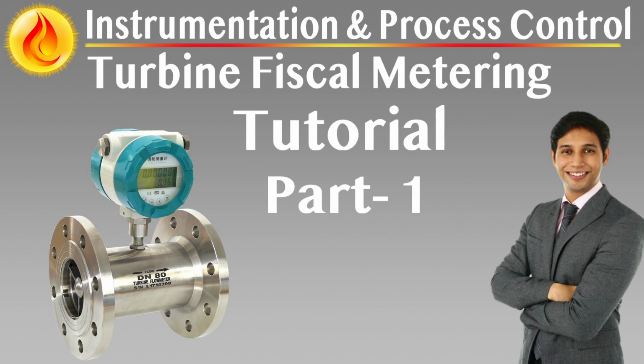At its core, turbine fiscal metering is designed to monitor liquid hydrocarbon flows with rigorous traceability and uncertainty bounds. The system is divided into two subsystems: the field-mounted skid with sampling and proving equipment, and the control and calculation infrastructure located in the CCR, LCR, or local room. This structure ensures operational transparency, enabling cross-verification of quantity, mass, volume, and quality (density, temperature, water cut) prior to final delivery. The entire measurement philosophy must be vetted early by authorities to ensure fast-track acceptance and error-free custody transfer.